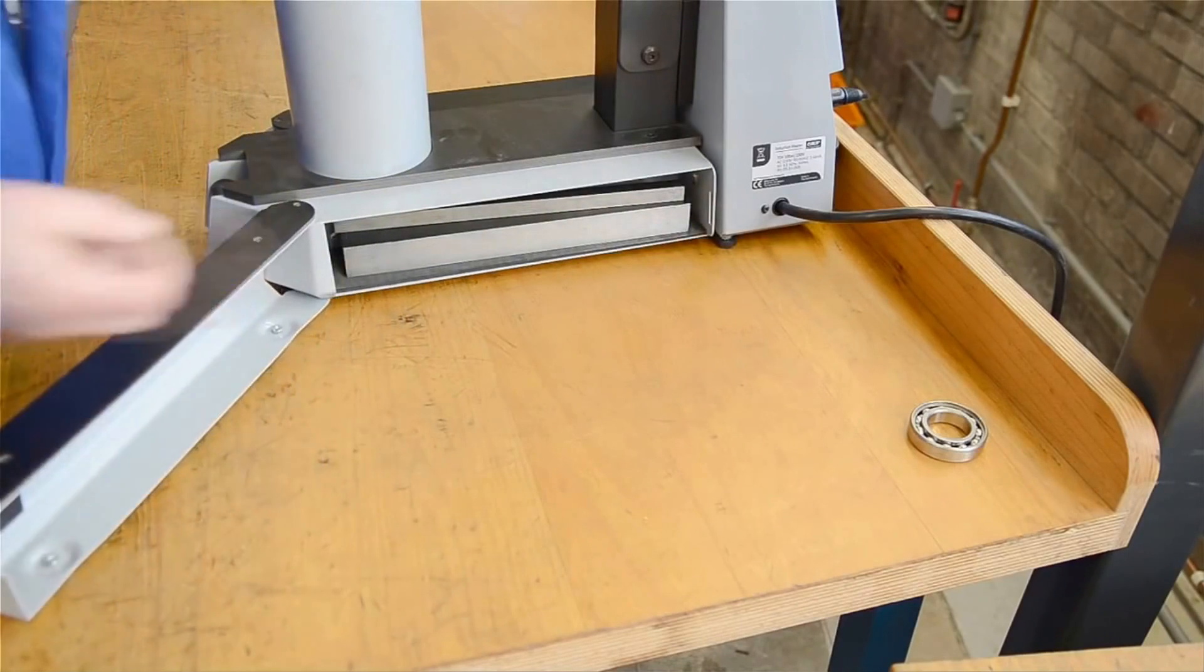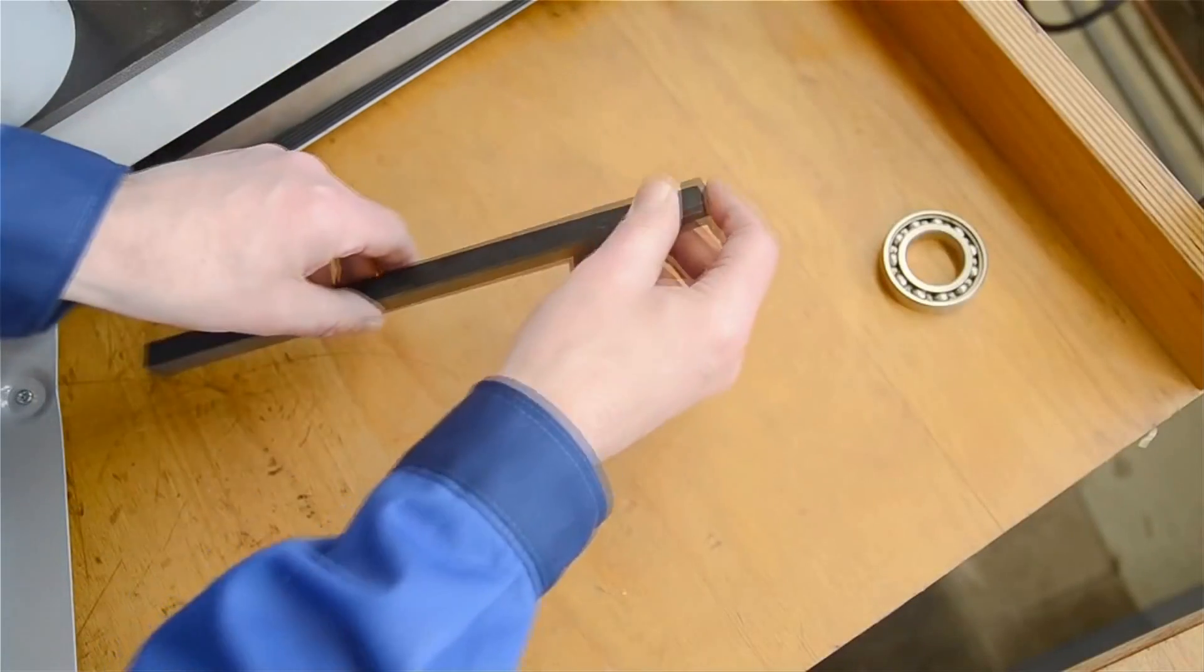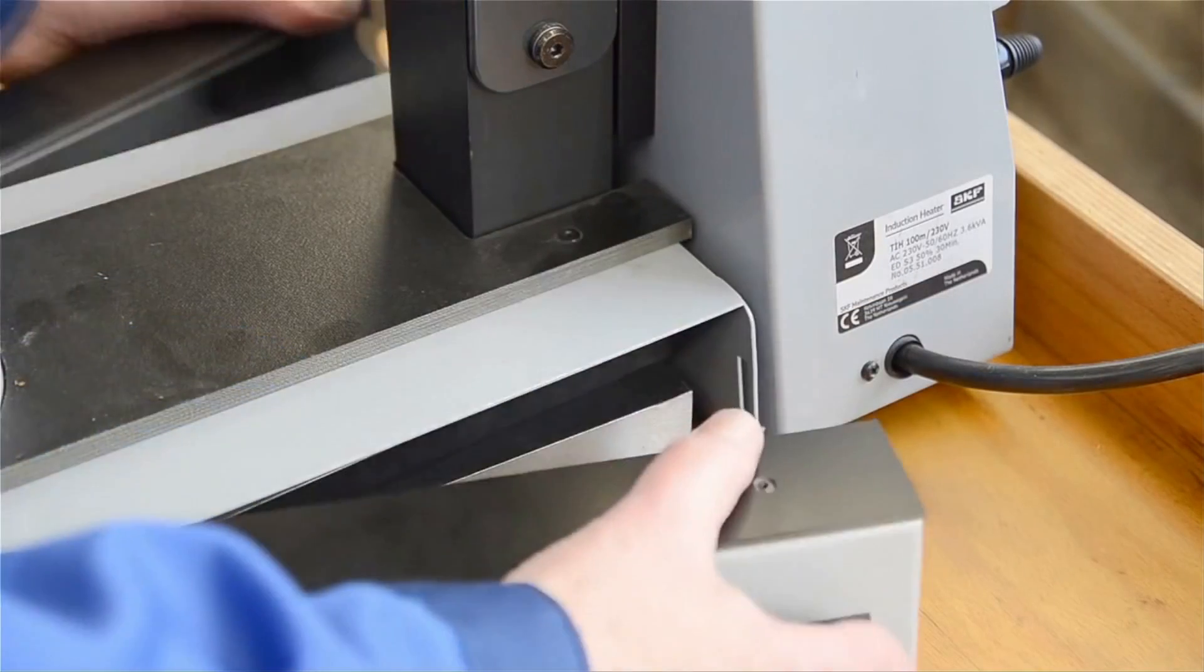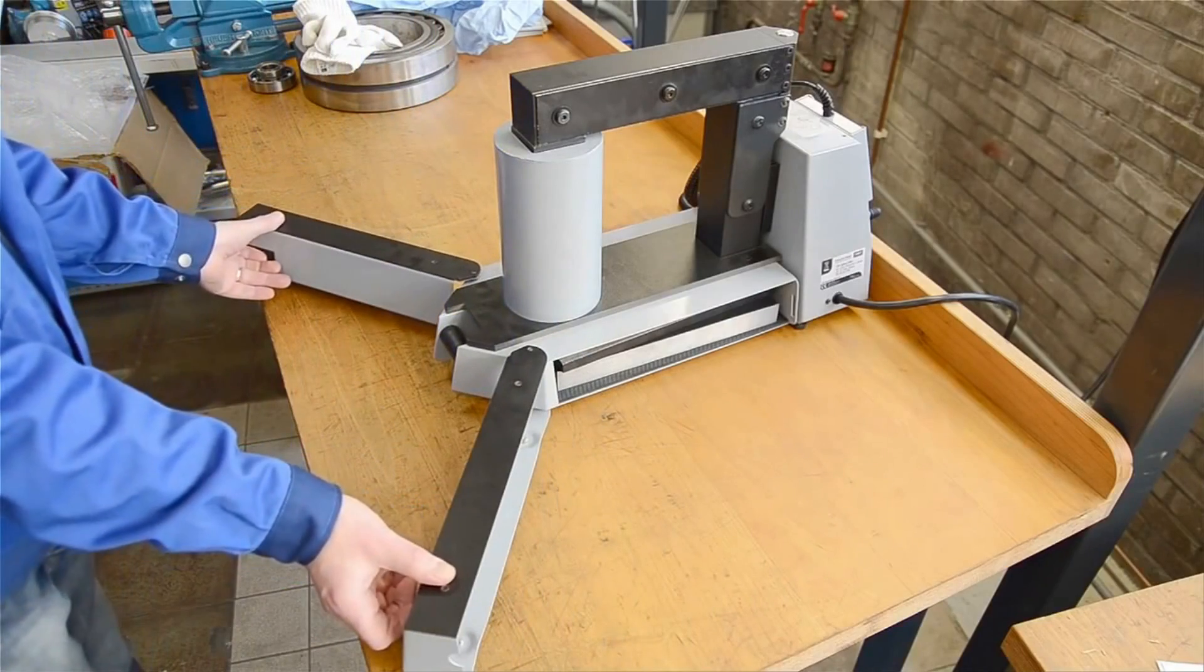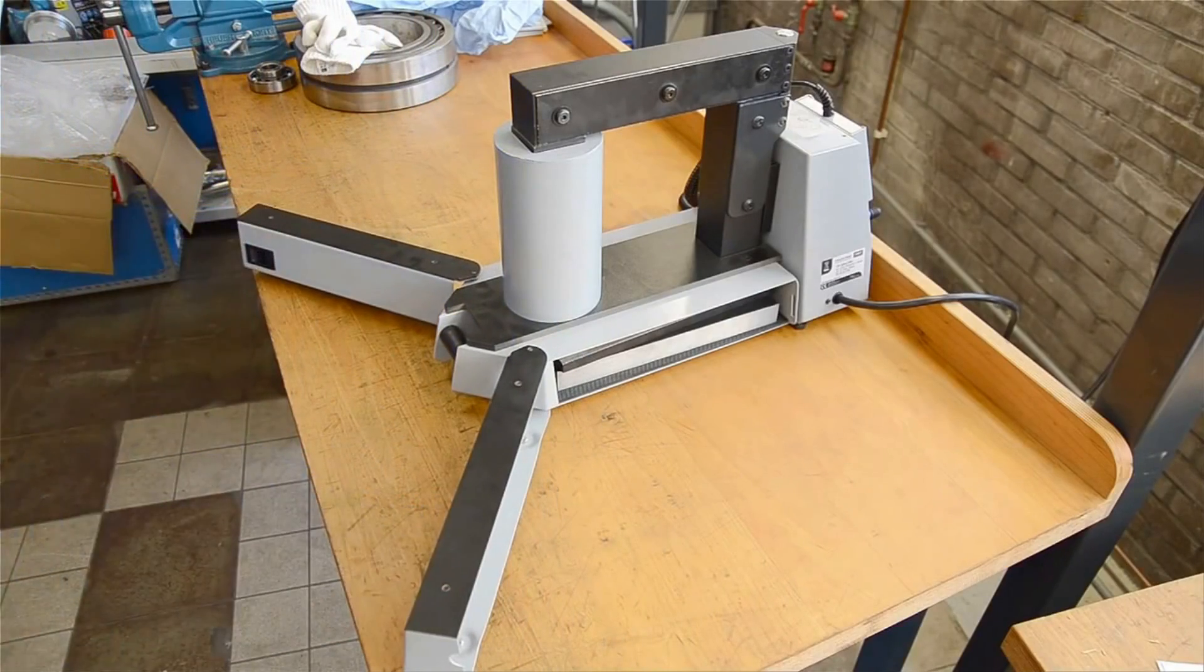Choose the appropriate yoke for the bearing to be heated and just place the bearing on the yoke. Better still, if there is space around the coil, then place the bearing here for even higher efficiency. SKF heaters have built-in adjustable support legs to make this option really easy.